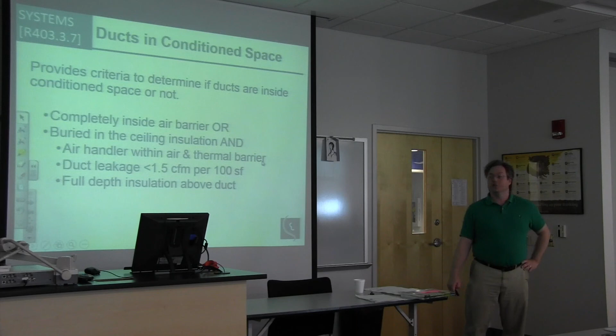I think that's the issue. Putting it above it, I mean, you can get it on top of the duct, but it's coming around it, the 3 foot, that you've got to dial up too. Because it's duct 3 to 4 CFM, and this is saying you have to be 1.5. So it's going to be tight. Otherwise, your ducts are not in the conditioned space, and then you have to test them.